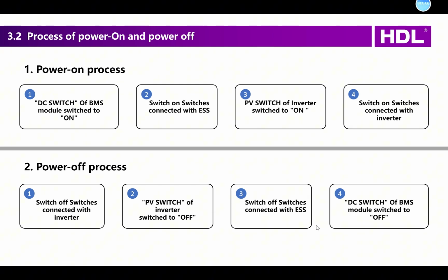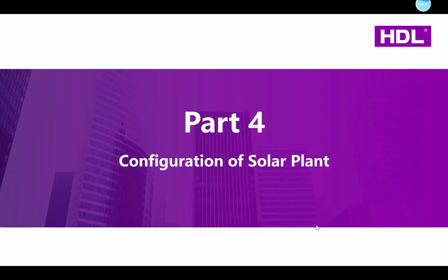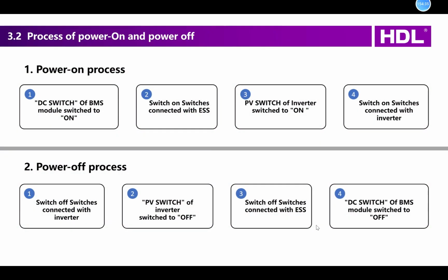For the power off process, it is reverse. So first you need to switch off the switches connected with the inverter, and then switch the PV switch of the inverter off. After that, you switch off the switches connected with the battery storage. And the last one is to switch off the DC switch on the BMS module. Okay, so this is just a simple instruction. So the installation part is very quick and simple.